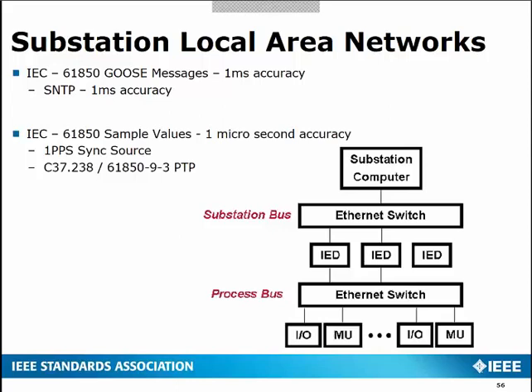New technologies such as 61850 with GOOSE messages or 61850 with sampled values are requiring accuracy. GOOSE messages, which are generally digital messages, sometimes analog messages between devices within the control house of the substation, require 1 millisecond accuracy. SNTP has been able to work with that, but it is not sufficient for the sampled values of devices that collect analog data from devices out in the yard, such as the current transformers or the potential transformers, the many sensors that all must be synced up. Those devices can be synced up with a 1 pulse per second locally, but you still need to get that accurate time to those devices. That's where C37.238 or 61850-9-3, the precision time protocol, will make things much easier.